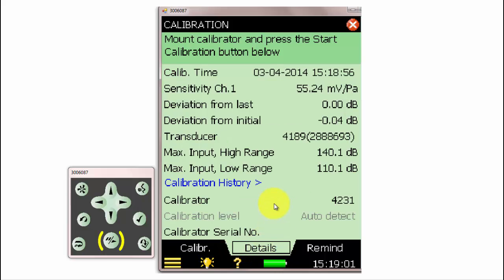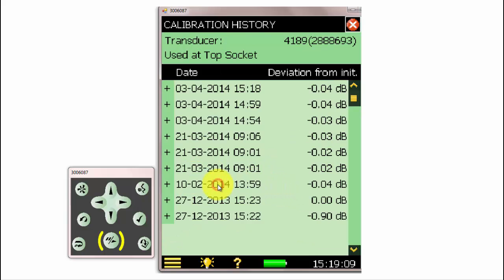Under the Details tab at the bottom, we can take a look at the details of the calibration. We can click on the calibration history to review the log of all the calibrations made on the meter with that transducer.